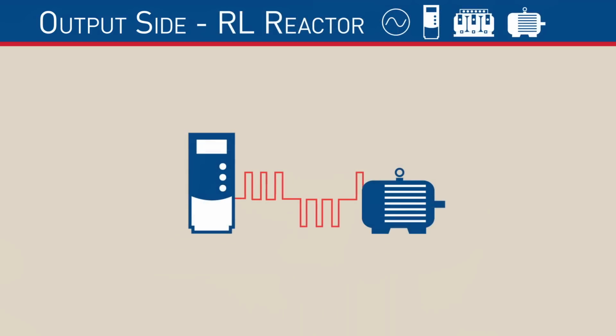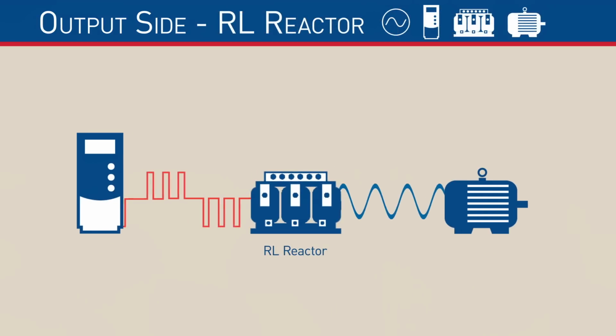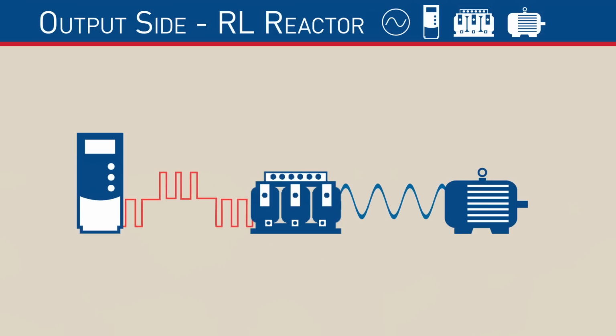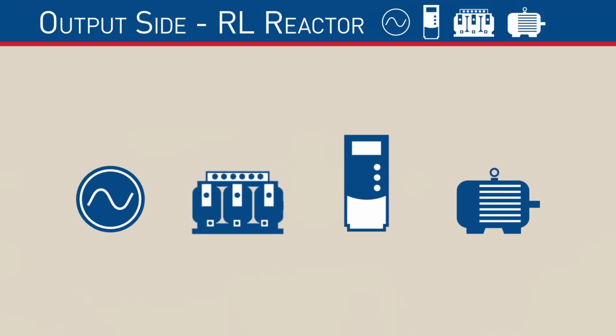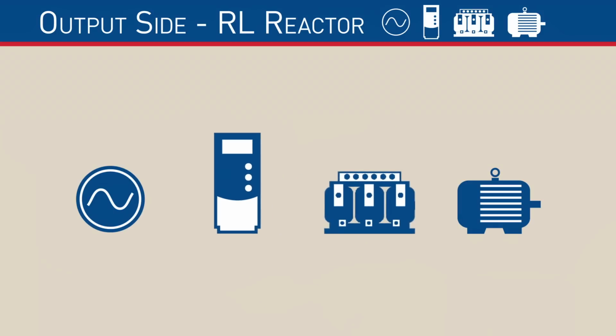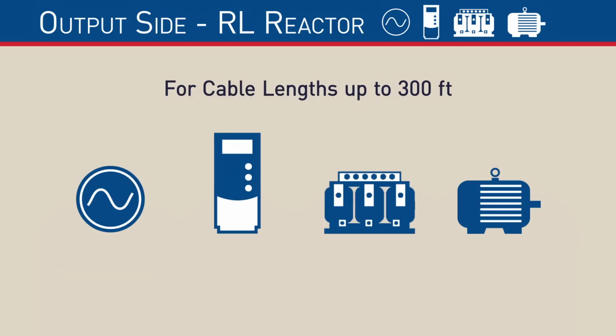Our first line of defense is to add MTE's RL reactor between the VFD and motor. Due to its unique design, the same RL reactor we used on the input side can also be used here on the output side without any derating. For optimal performance, the RL reactor should be used for cable lengths up to 300 feet.